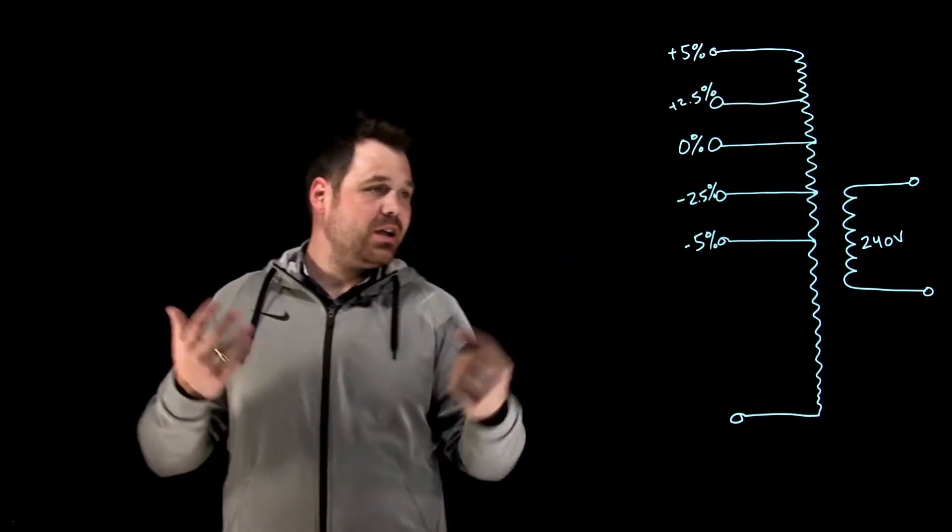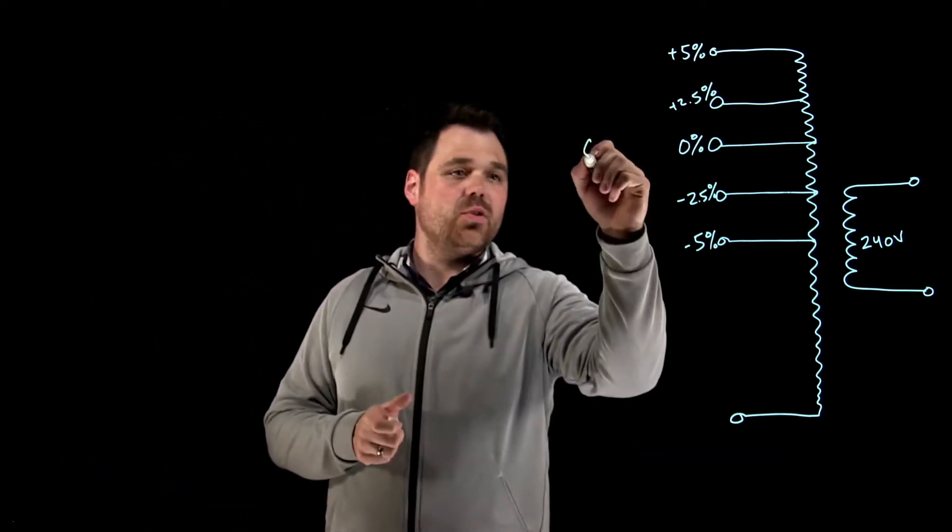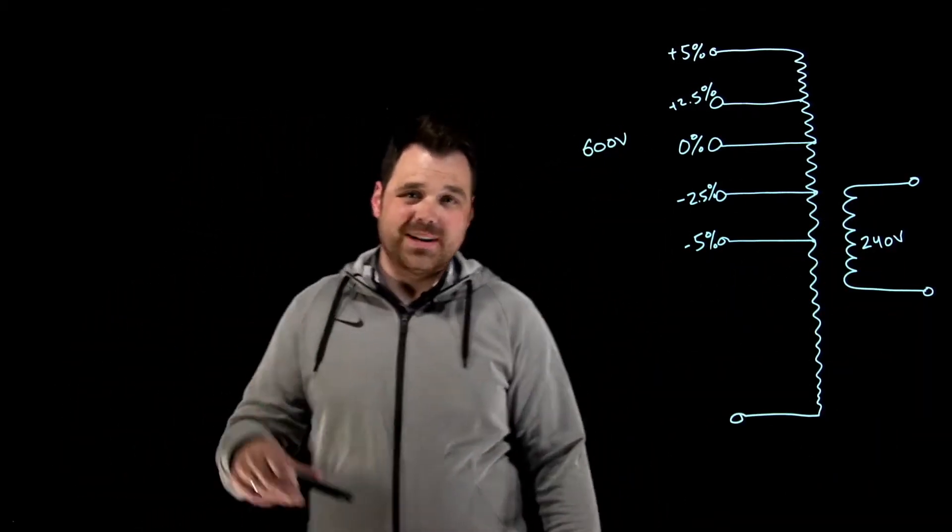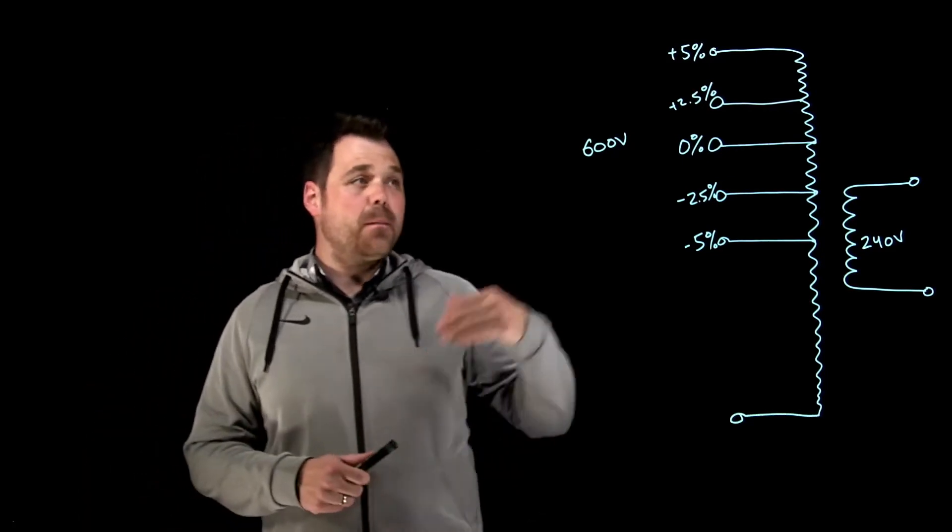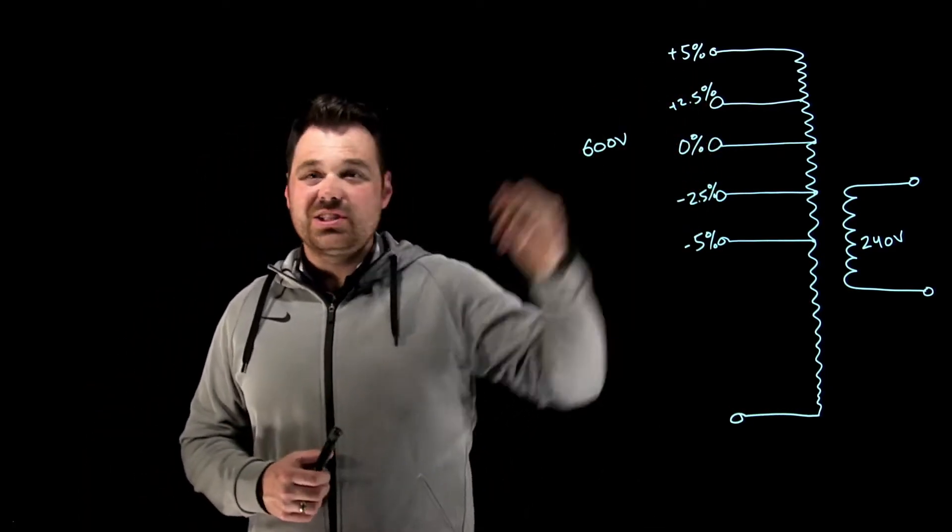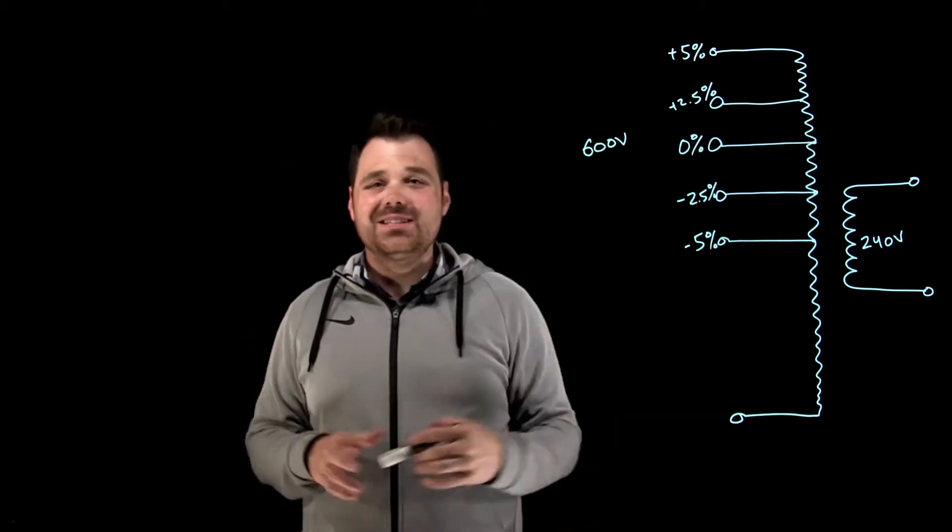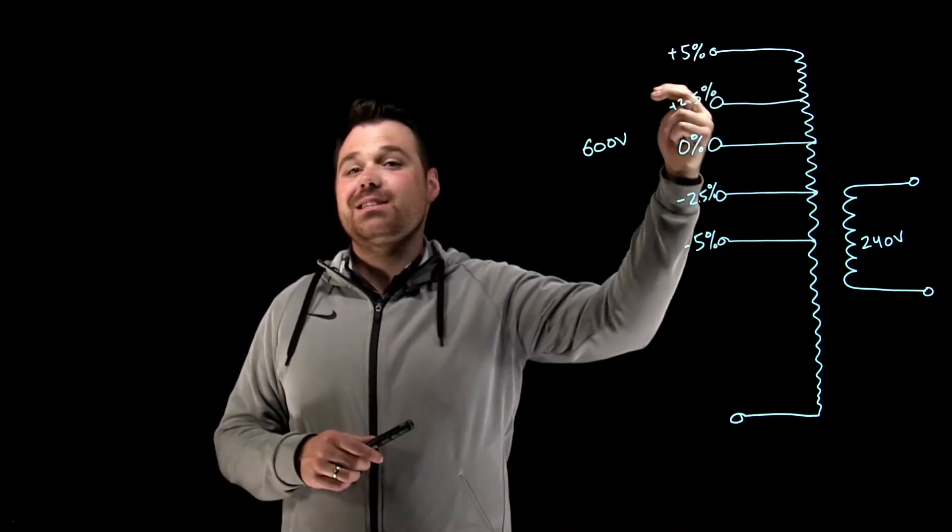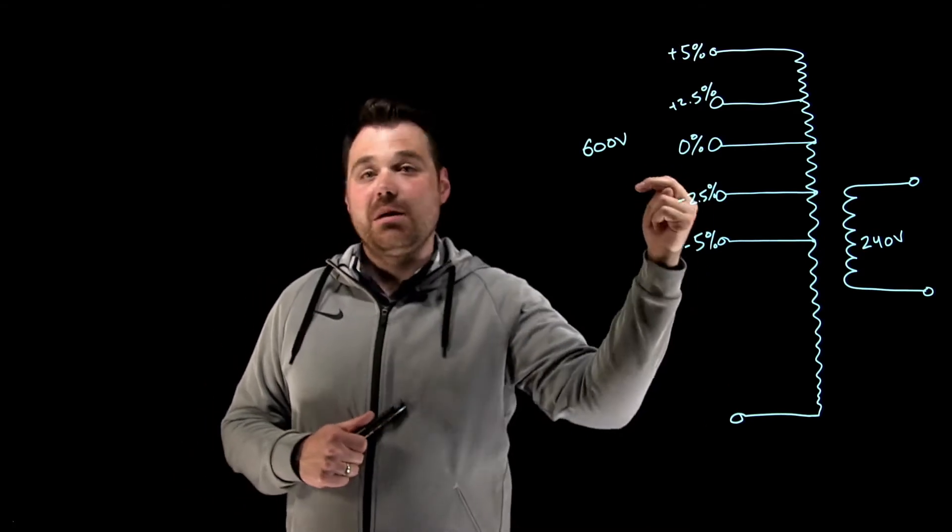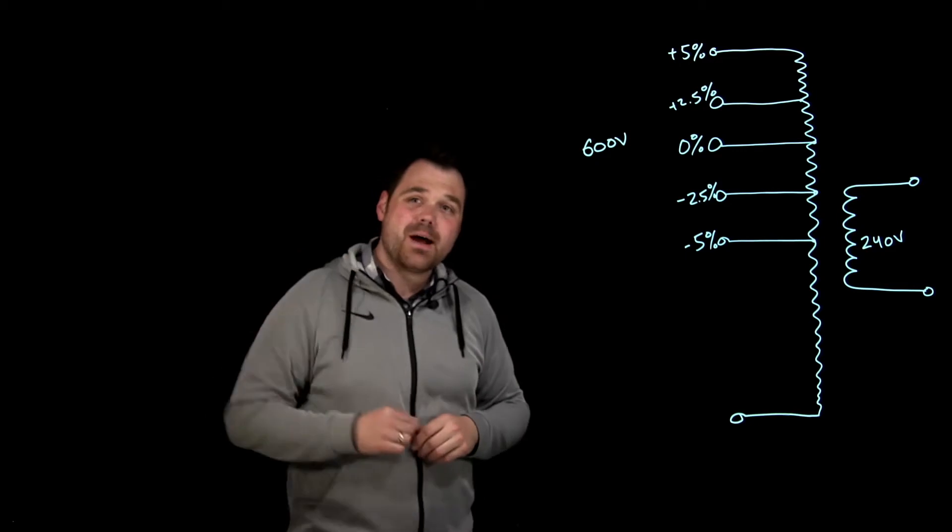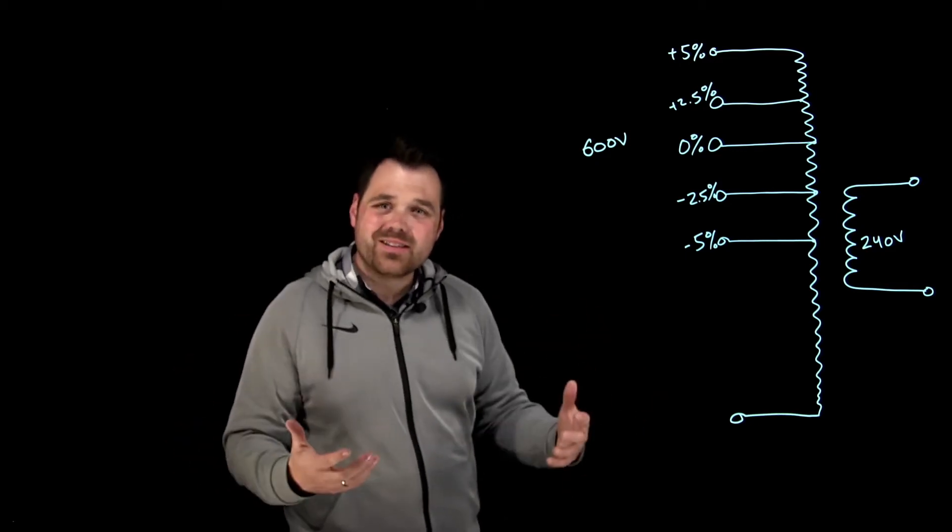Here I've got a 600 volt rated down to 240 volt transformer. Now what we see here on the primary is we see these little taps with labels, sometimes they're three, sometimes they're five, whatever they are. In this case, I've got a plus 5%, plus two and a half percent, minus two and a half percent and a minus 5%. Now these are voltage taps. What's the purpose? Why are they there?